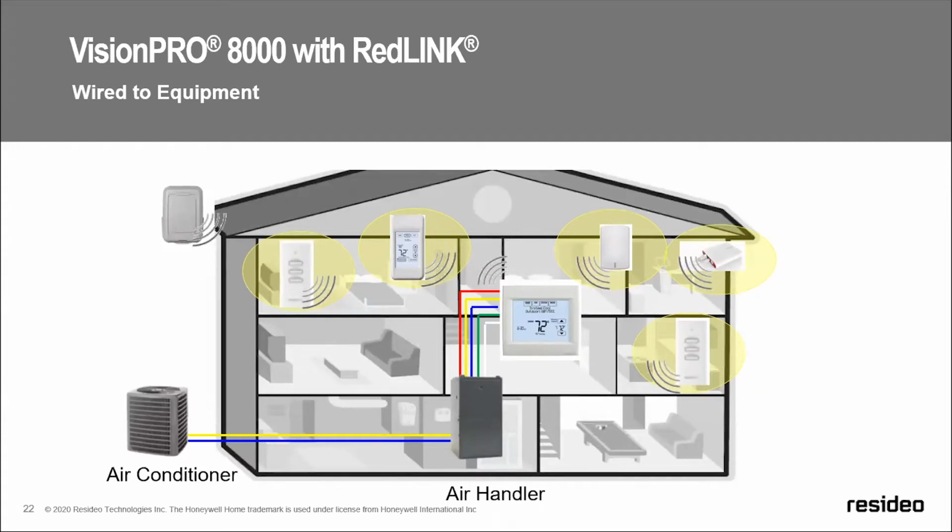Very simple. You would set up your 8000 as the host when you're doing your setup and then add whatever accessories you need. So in this scenario here, you've got plenty of wires down to the furnace and out to the air conditioning unit, but you need to do some certain things to make the house a little bit more comfortable. You can add a PCC or an indoor sensor. Here's the rule of thumb for our averaging of our indoor sensors for RedLINK: you can use 5 if you use the thermostat face itself as a temperature and humidity sensing point. If you decide that you don't want to use that, you can do 6. And what that'll do is it'll average all of the indoor sensors and it'll run the system appropriately.